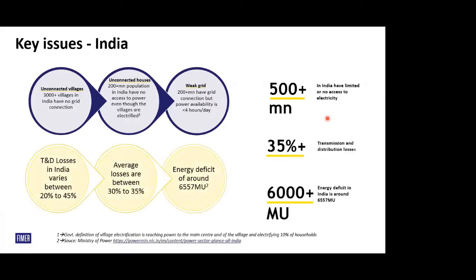The second very interesting and major issue that India faces is transmission and distribution losses, which vary between around 20 to 25, 45%, where the average loss is around 35%. Technically this might not be the losses per se in the grid, and it also includes something called theft, which cannot be shown as theft, so they show it as a transmission and distribution loss.